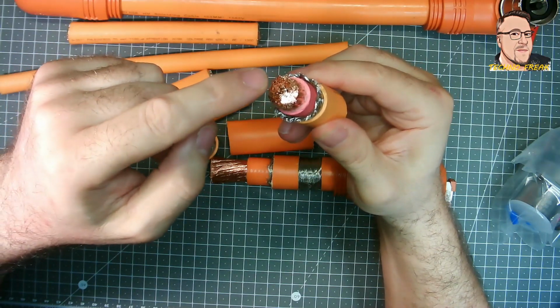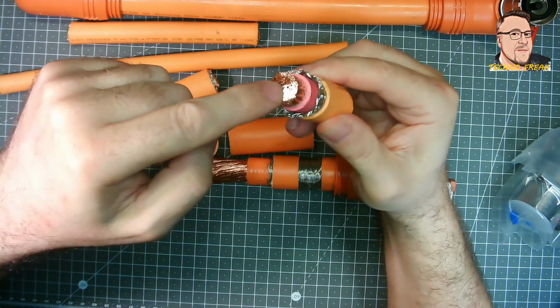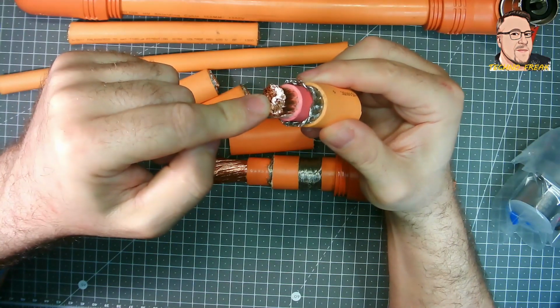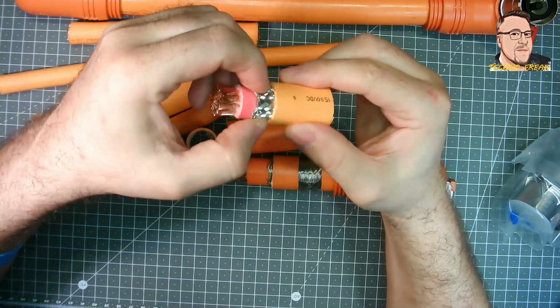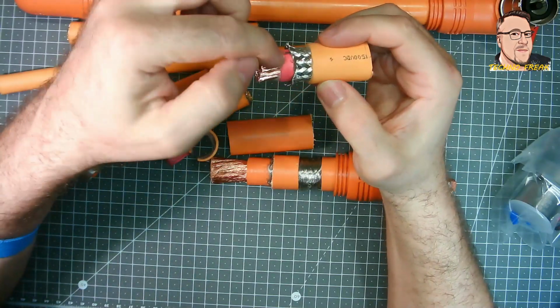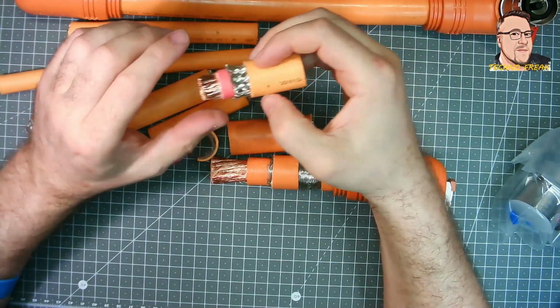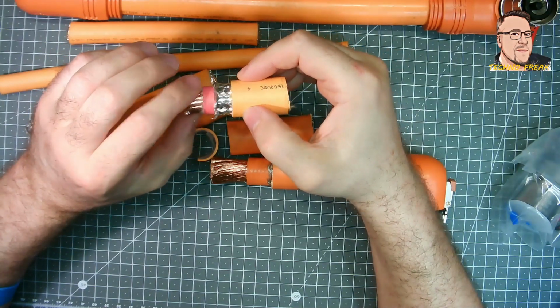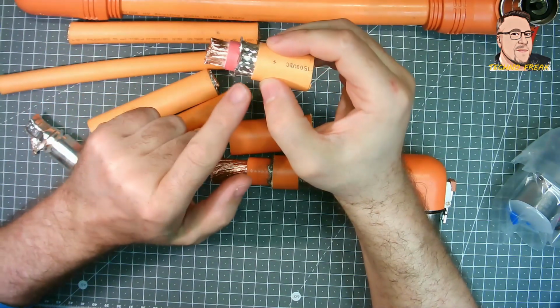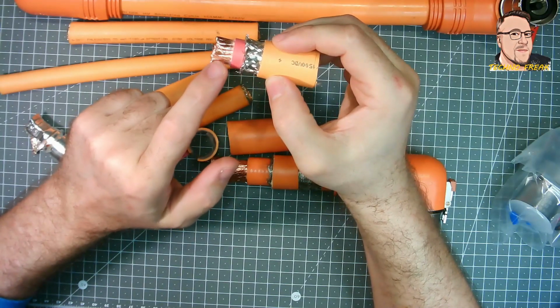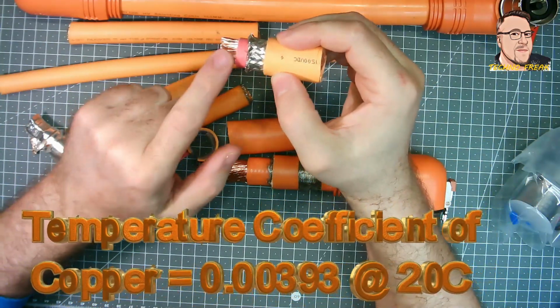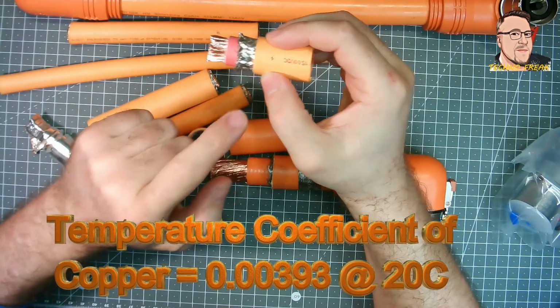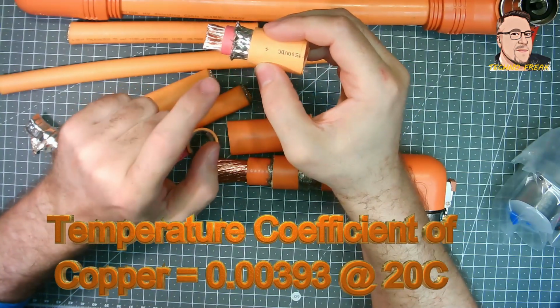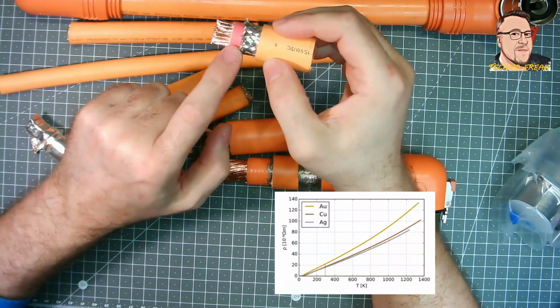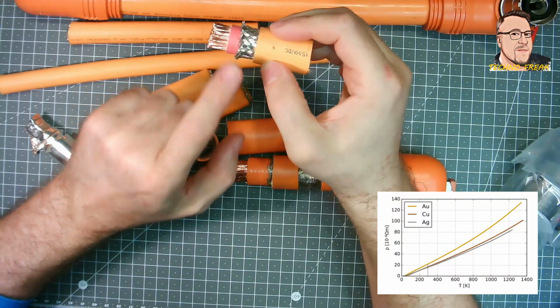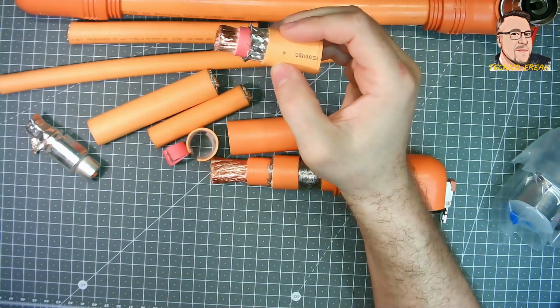That's the big difference between single core and multi-core cables, because a single core cable can dissipate much more heat. If you have a multi-core cable, the maximum current will be much lower. Always check the specification of the product, because different manufacturers could use different materials, and that could affect the maximum rating.